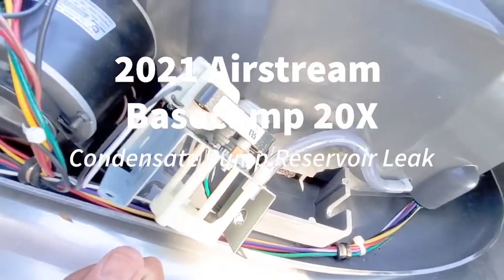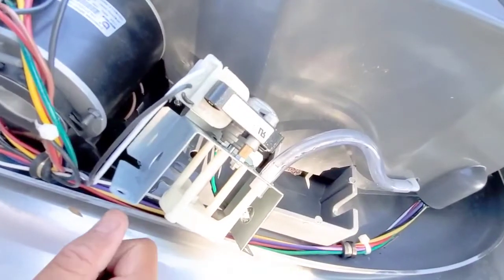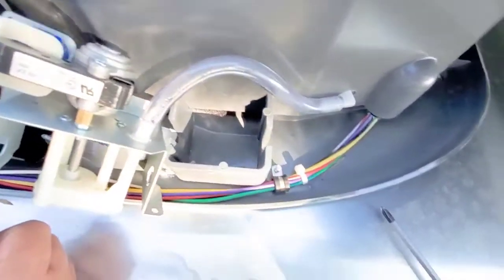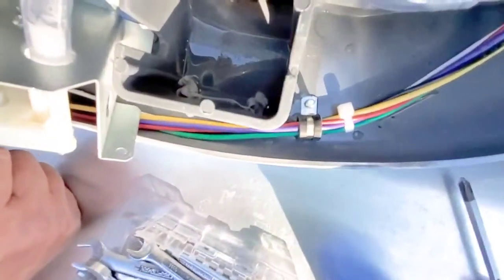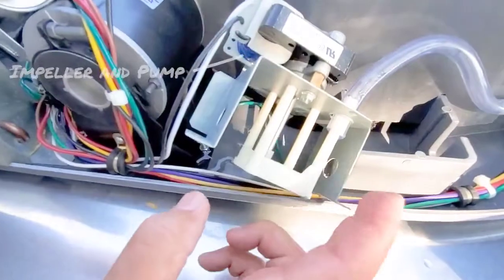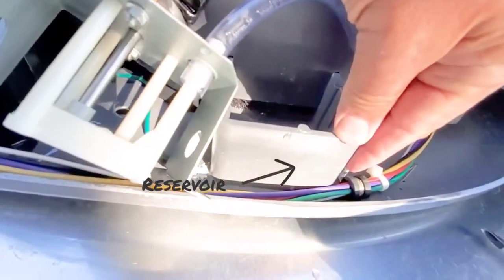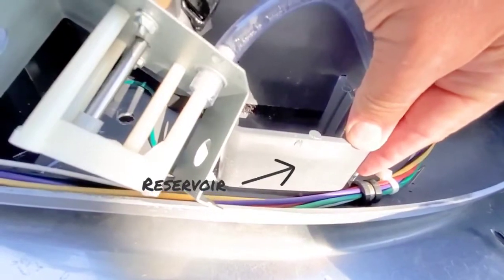I got up on the roof and I pulled the condensate pump after talking to Airxcel. I also saw a video online. This is the condensate pump right here, and this is the reservoir that holds the condensation coming from inside.